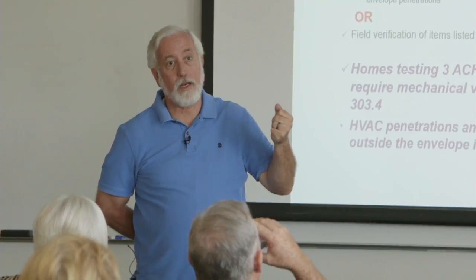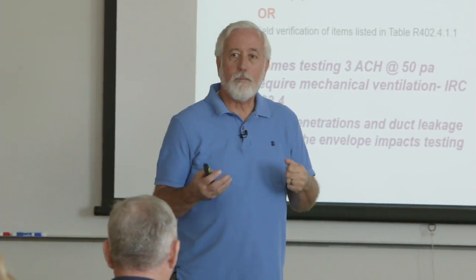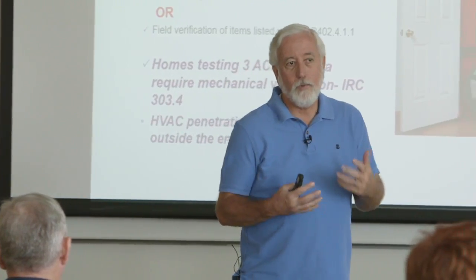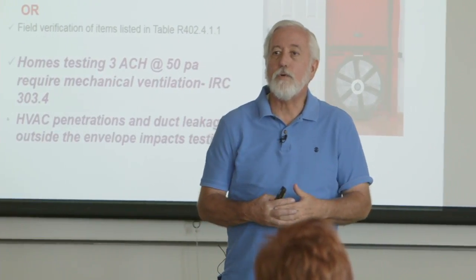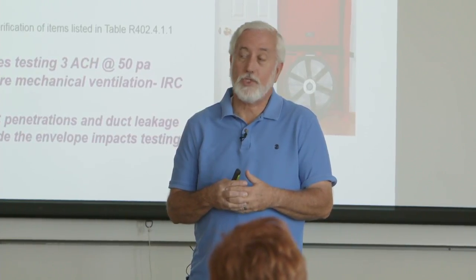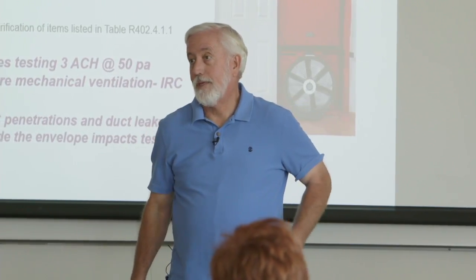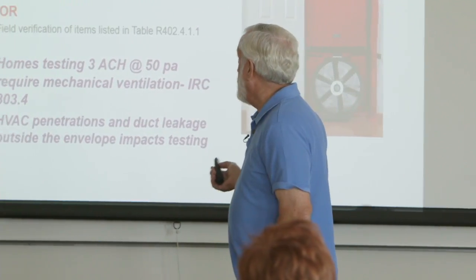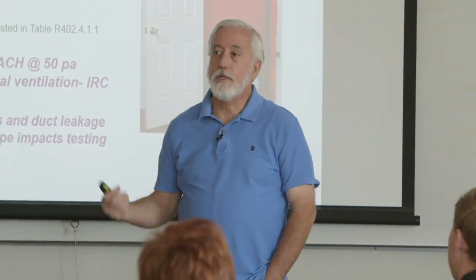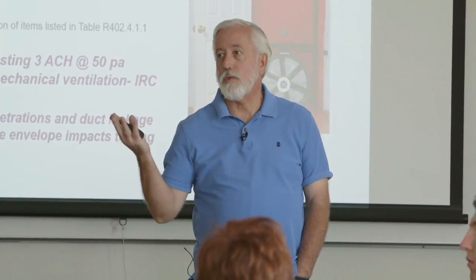The reason I say you should plan on it is because as we build a building tighter, even in dry Utah, we create moisture by living in our houses. We breathe, we bathe, we cook, we do all these things, and we create moisture within our house. And if we don't get it out of our house, we're looking for a potential problem. And we might not see it because it might be within our wall assemblies or something like that. So I would say, come January, I'll start teaching and preaching this, we really probably ought to be looking at mechanically ventilating those. We don't have to do HRV or ERV. That's not what the code says. We can do it with just an exhaust fan.